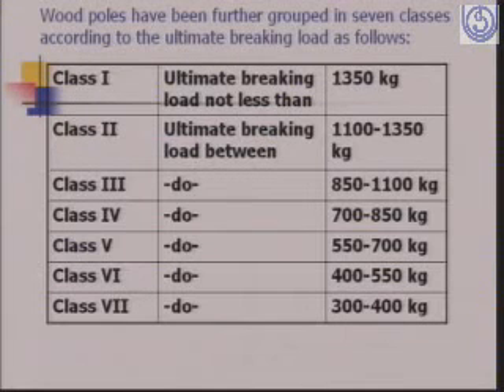They have further been classified according to the ultimate breaking load into 7 classes, like class 1, class 2, class 3, 4, 5, 6 and 7, and the ultimate breaking loads for these are indicated. Class 1 has 1350 kg, class 2 1100 to 1350 kg, class 3 850 to 1100 kg and so on.